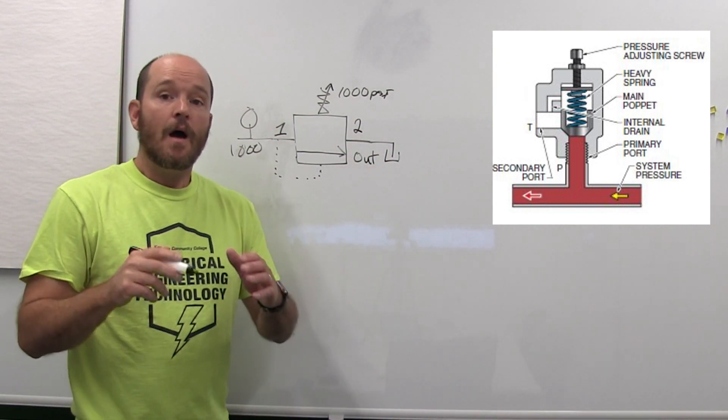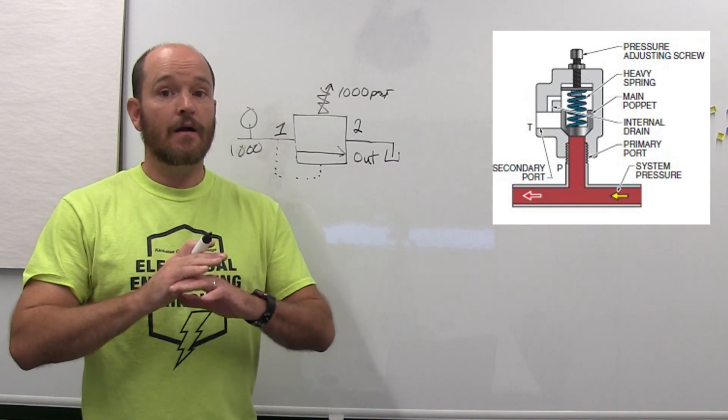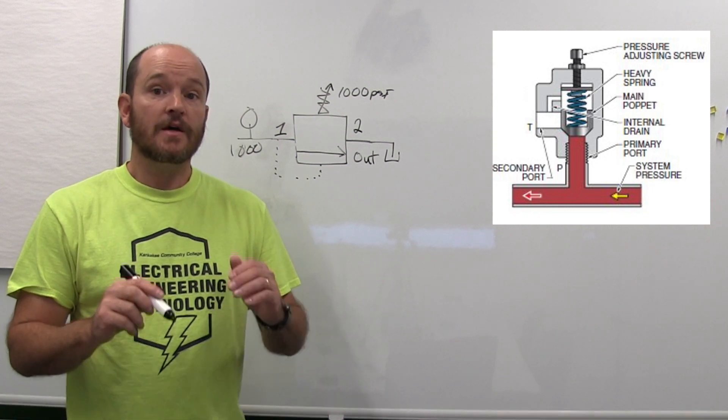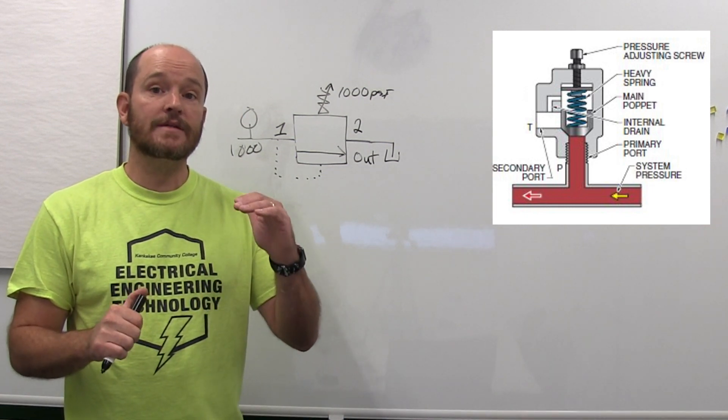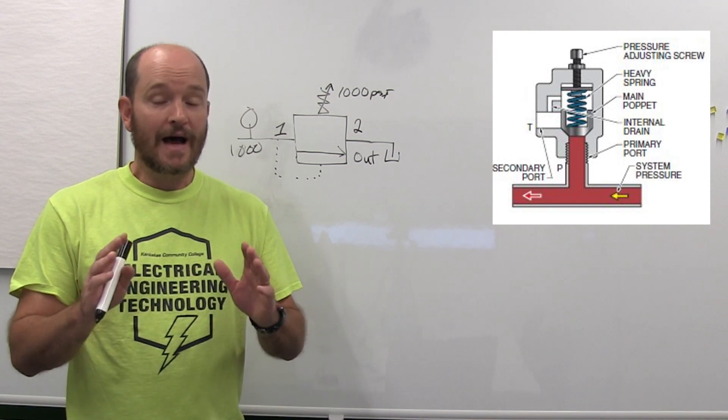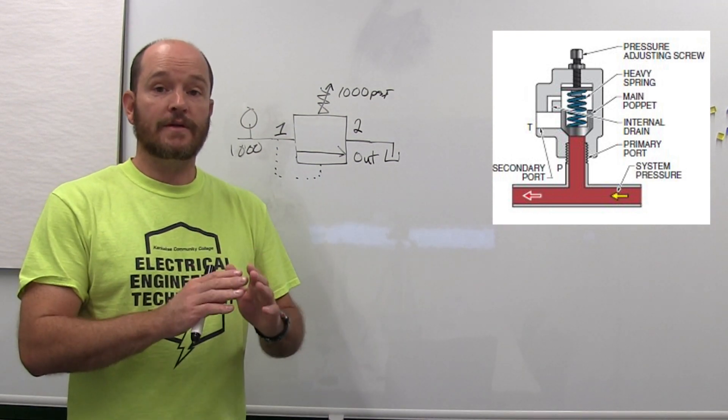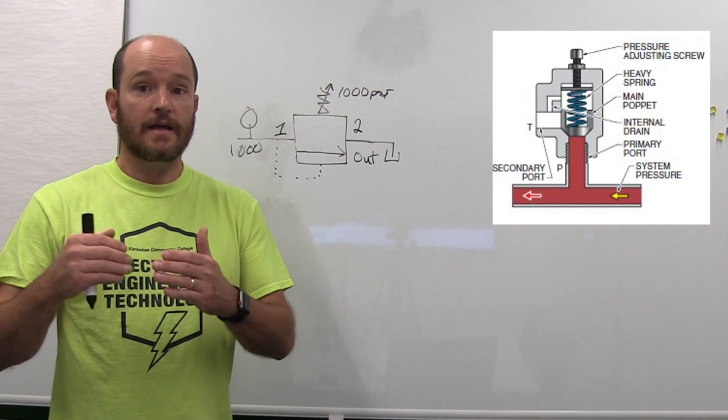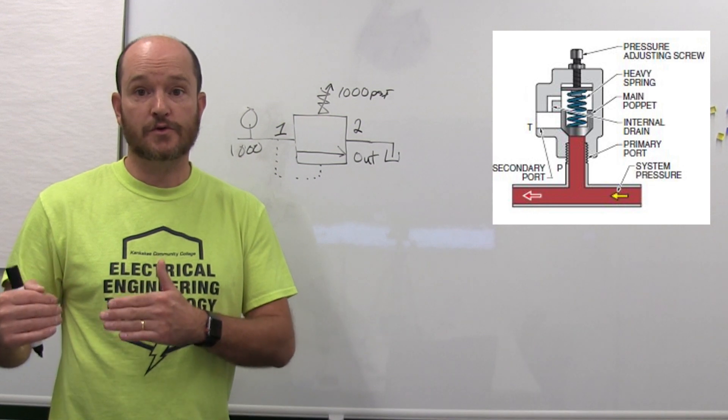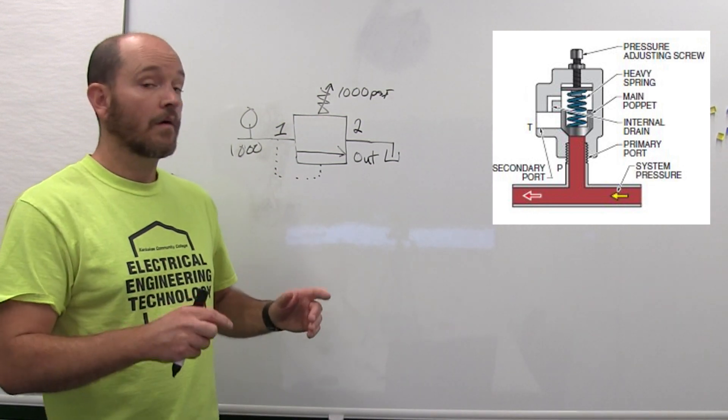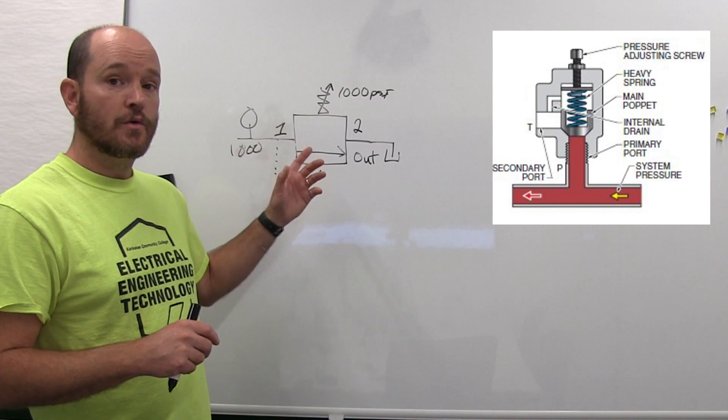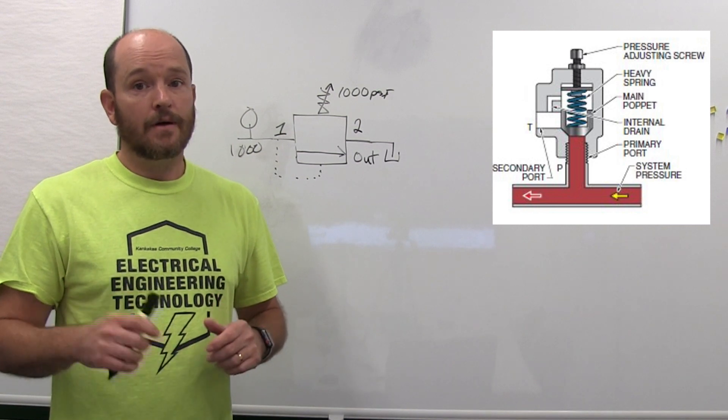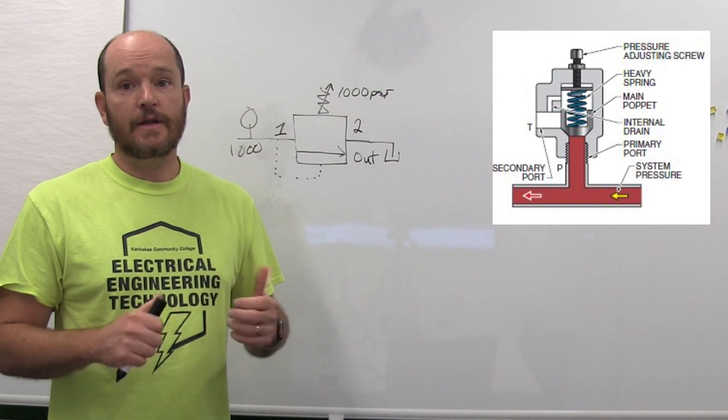Most if not all hydraulic systems require a pressure relief valve to set the maximum resistance in the system. Without one or if they go bad, you're either going to burn the pump out, the motor is going to pull more current than its protective devices can handle, or worst case scenario you could burst a hose that could cause damage to equipment.